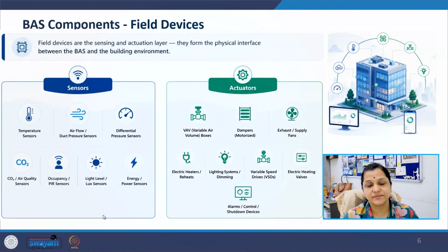Building automation components. They are field devices. Field devices form the physical interface between the building automation system and the built environment. So sensors collect information about indoor and outdoor conditions. Temperature sensors measure thermal condition, while airflow and pressure sensors support HVAC balancing and system control. Carbon dioxide and air quality sensors support ventilation management. Occupancy sensors detect human presence, while lux sensors measure daylight intensity for daylighting control. Energy and power meters monitor electricity consumption and operational performance.